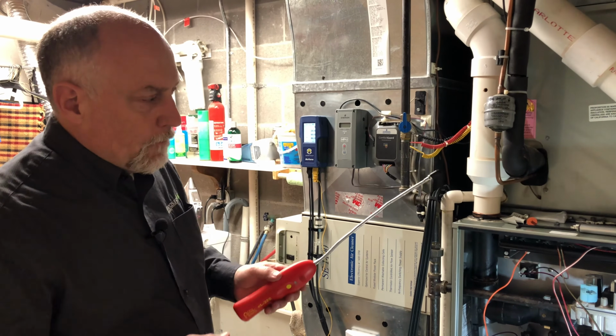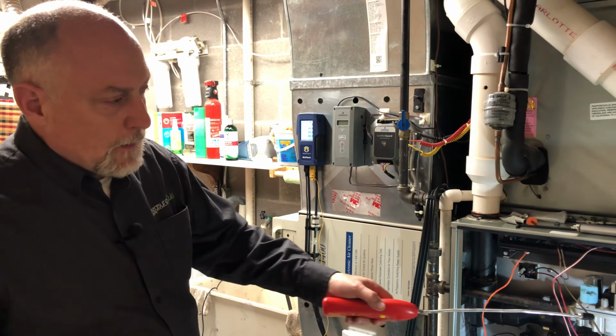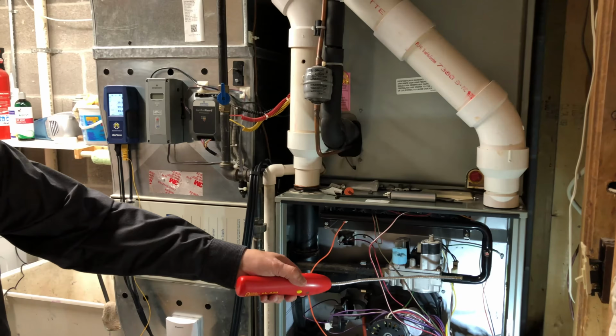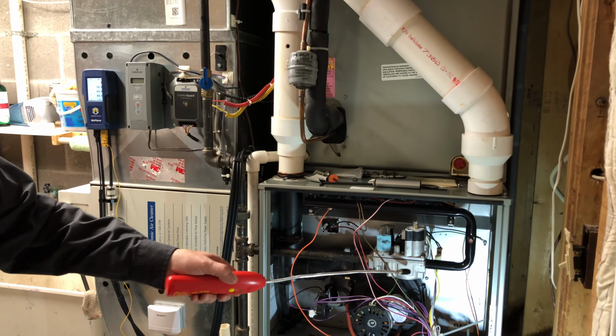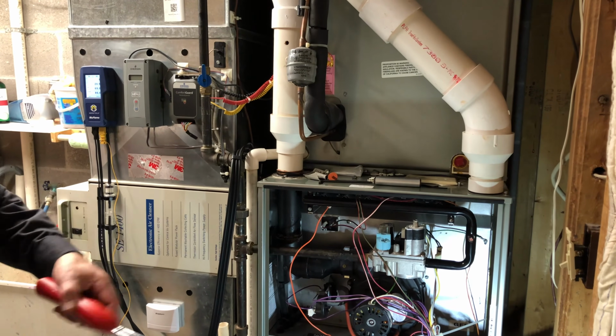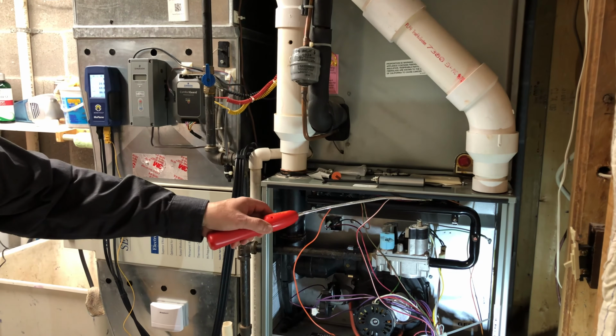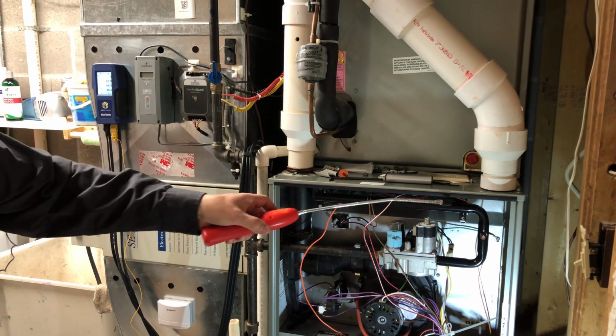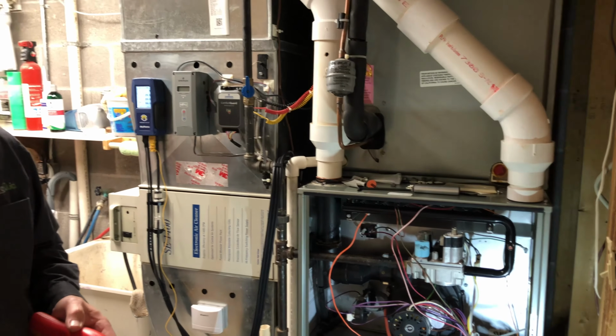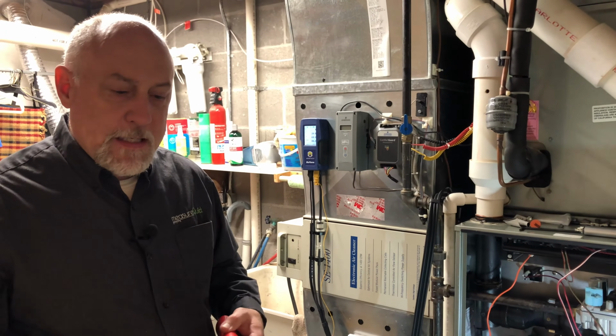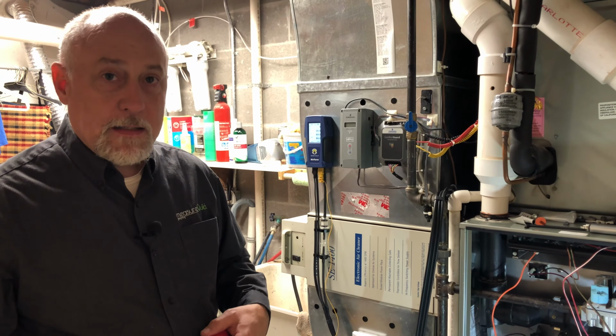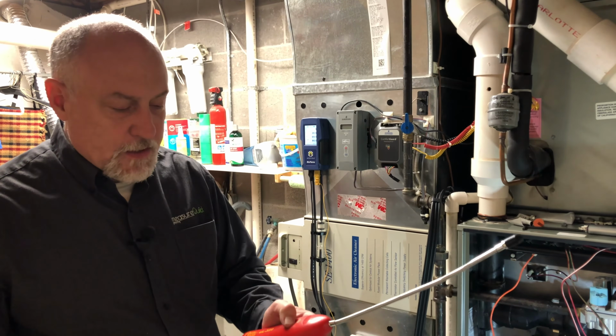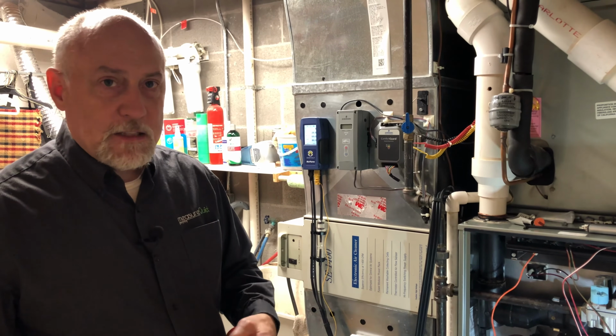I'm going to show you, the furnace has been off for a few minutes, but there is natural gas in this manifold. When the gas valve shuts, there's no place for this gas to go, and it will slowly leak out. I'll put this up here and see if we pick up a little gas. And you can see we're still picking up gas, and you'd think maybe your gas valve's leaking, but it likely is not. It's just that the sensitivity is so high that it picks up any gas in the area.